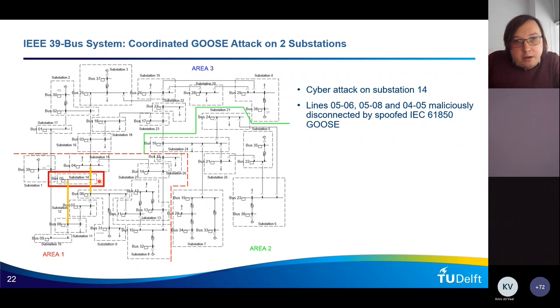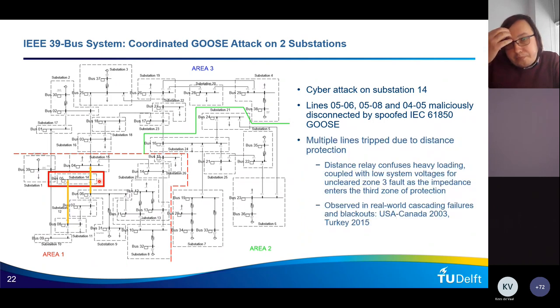And then the impact of it is that 3 lines are maliciously disconnected by this cyber attack. Now, what would be the impact on system operation? Well, multiple lines would be tripped due to distance protection. The reason for this is that the distance relay confuses heavy loading coupled with low system voltages for an uncleared zone 3 fault, because the impedance enters the third zone of protection.